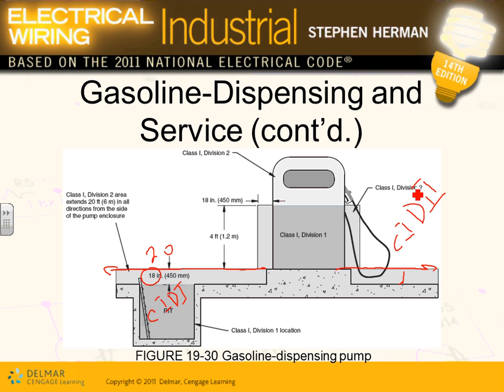So when they do the gas station, they use rigid threaded metal conduits coming all over into the gas pump. Inside the pump itself, if you enter the pump, it's class 1 div 1, the worst of the worst. Around the pump in all directions, up to 18 inches, it's called class 1 div 2. So avoid putting anything electrical around the pump, or it has to be an intrinsically safe system or explosion proof. Any comments, guys? Any questions?